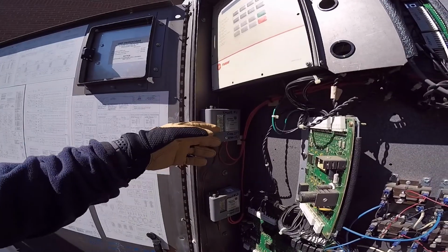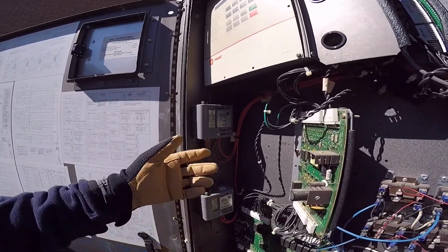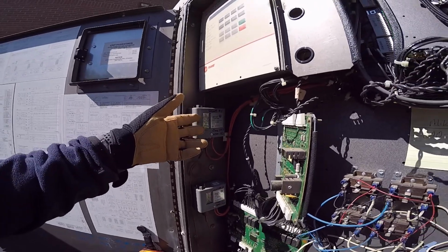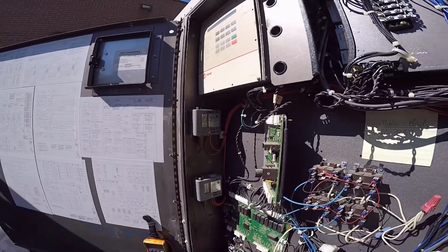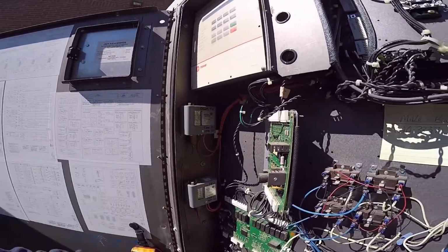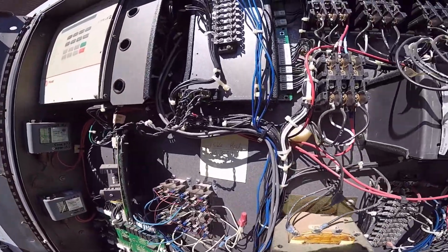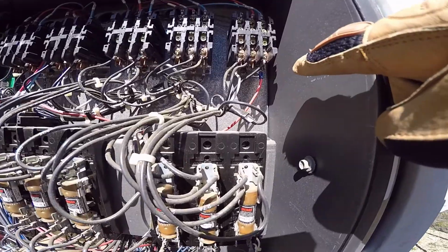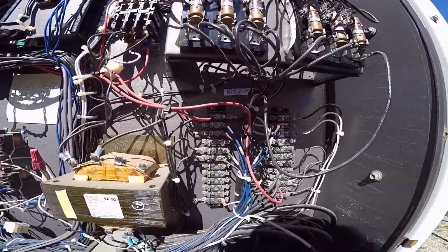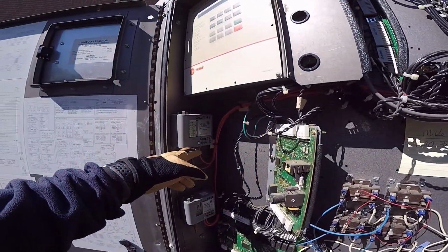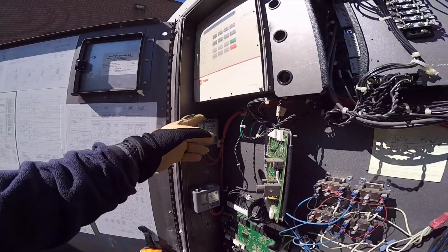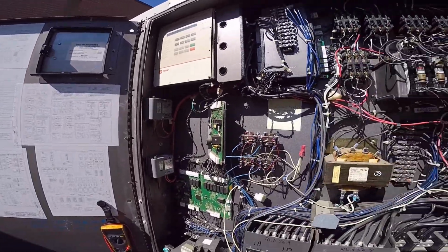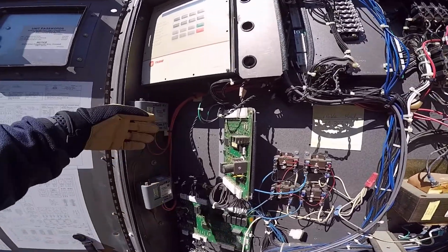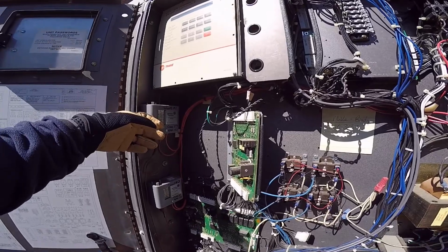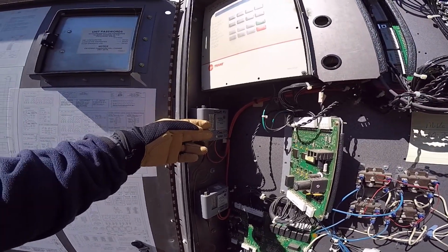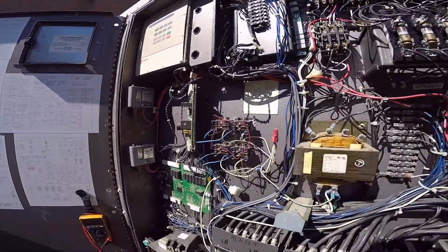This unit doesn't have VFDs, so we're trying to control the condenser pressure by using pressure switches. What that allows us to do is set the opening and closing of the switch, and you can follow the red wire on the coil. You can follow that red wire down to the terminal block, and then it comes over to the pressure switch, and then it goes to the board where it's activated. So all we're doing is breaking the circuit that pulls the coil in, and we get to decide what pressure we're breaking that at.